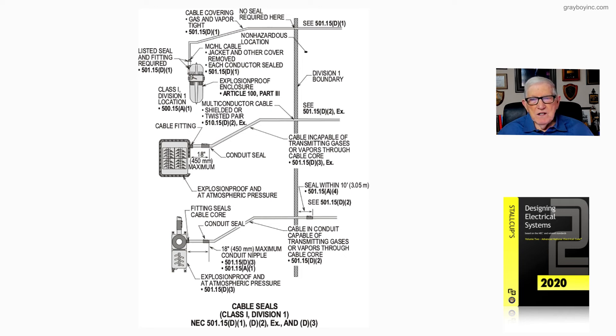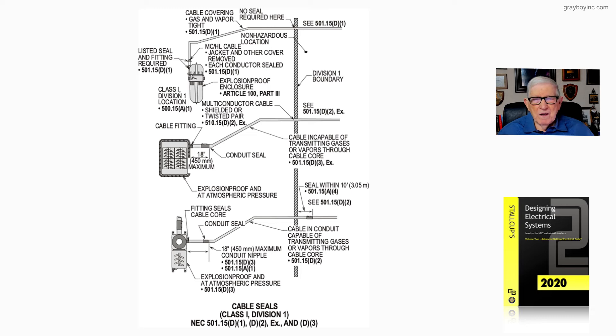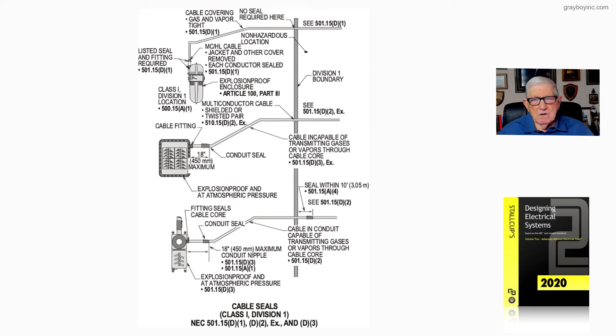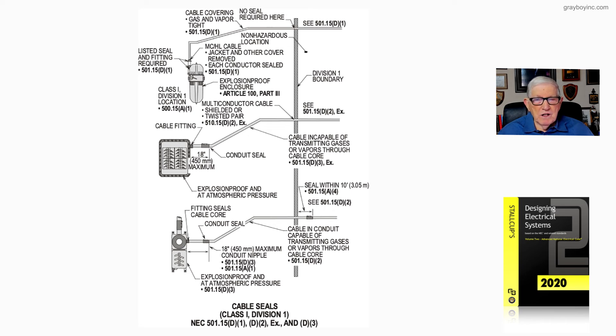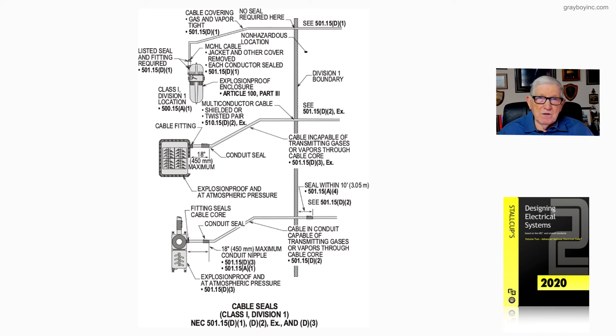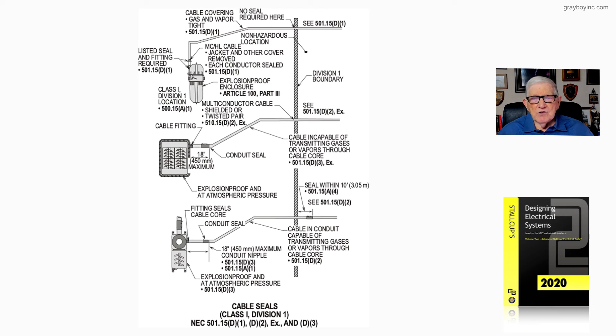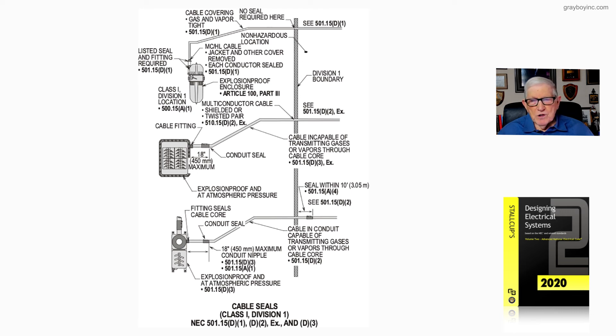We find this 18-inch rule of sealing in 501.15d3. We pick it up in 501.15a1, and the explosion-proof equipment installed at atmospheric pressure conditions we find in 501.15d3. That's what the illustration is demonstrating to the NEC user regarding where cable seals are needed.